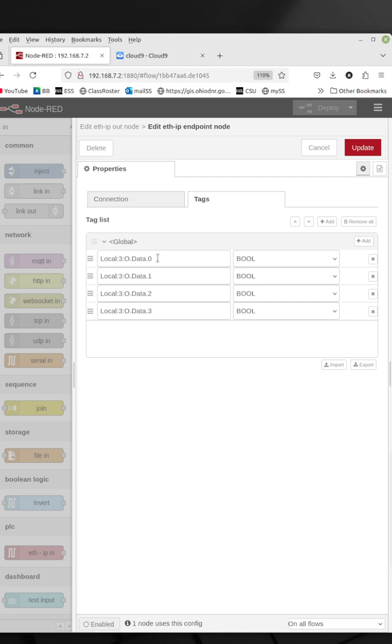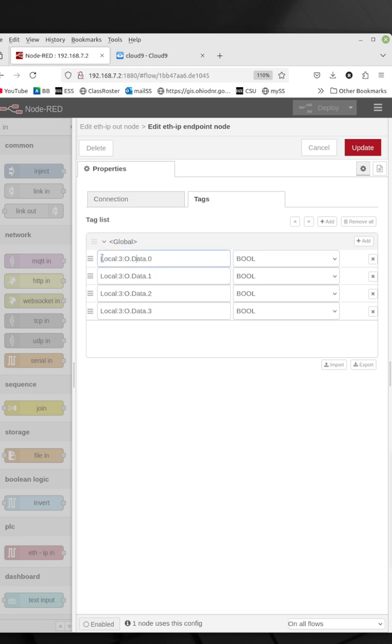If you're using the physical modules, you have to make sure it's a capital L for local. The module number is correct. You have to have a colon on both sides of the module number here, the left and right of the three. And then you have to have an O for an output. It needs to be a capital O, not a zero, not a lowercase O, a capital O. You've got to have a capital D. Now if you're doing an input, if you're trying to bring something in, then your tag would be a capital I for input. And then of course, you have to have the right bit number if you're doing Boolean.